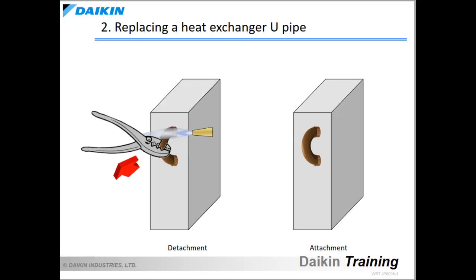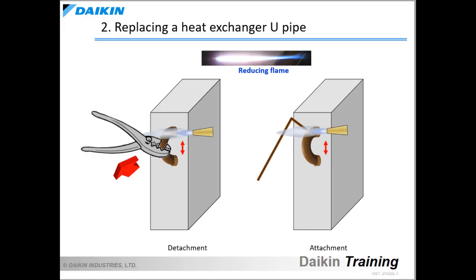Let's now learn about the procedures when replacing a U-pipe because of a problem such as a hole or deformation. Use the reducing flame. Adjust the flame to a low intensity. Detach the U-pipe by alternately heating the two connection areas with the flame. When attaching the U-pipe, alternately heat the two connection areas with the flame and insert the pipe all the way in. After inserting the pipe, distribute the brazing filler metal from behind the joints. During the actual work on site, be sure to conduct nitrogen replacement to prevent the inner surface of the copper pipe around the brazing area from oxidizing. Note that nitrogen replacement is omitted here as the purpose of this course is to learn about the points of brazing work.